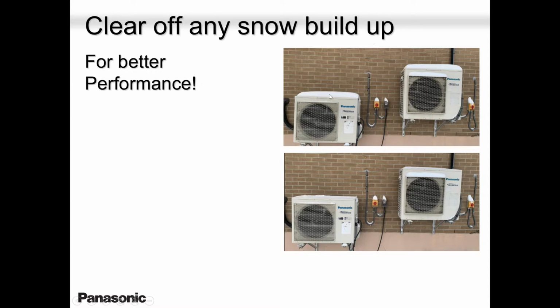The top one was before and the bottom one was after. I cleared the coil. I cleared the ice, the snow. And this is what you need to tell the homeowner. That's why I brought this picture. So please, guys, I want you to do this, and I want you to explain to the customer, even if you're installing it in the summer, you may not go there for the next 5, 7, 10 years. So always tell the homeowner, if you're dealing with homeowners, that this is your responsibility. Just like your driveway, this is part of your responsibility. If the customer is worried, switch it off, clear it, then switch it back on.